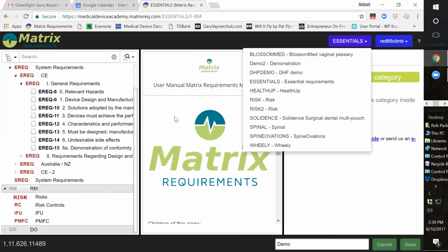Some people will ask, do I have to pay to validate the software? No, you don't, because the company that developed it, they're validation experts, and because it's a web-based software, the only people that can validate it are the people that host it. Whereas if you bought CDs and you loaded it on your server, then you'd have to validate it. So that's one of the things I recommend to companies is only buy web-based software in medical device, because otherwise you have to pay to validate it, and that costs a pretty penny. Understood. Okay.